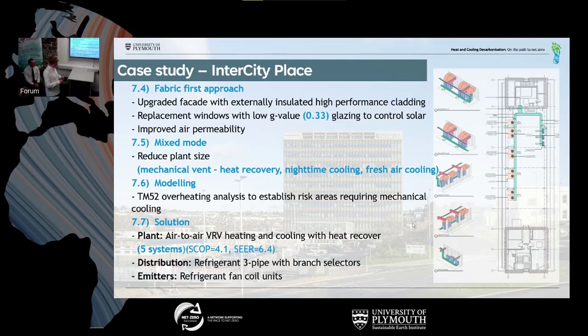Why did we do that? Because it's actually a very efficient technology with variable drive inverters, so it can match low loads, not just high loads. It also has the opportunity for heat recovery - it's a three-pipe system. They use a high-pressure gas which provides heating, and a high-pressure liquid which can provide cooling. The third pipe is a low-pressure gas, which goes back to the outdoor unit.